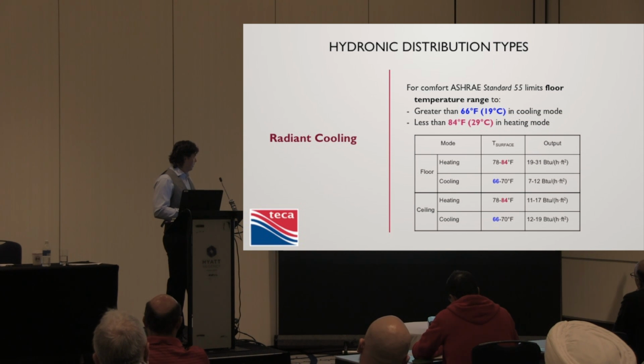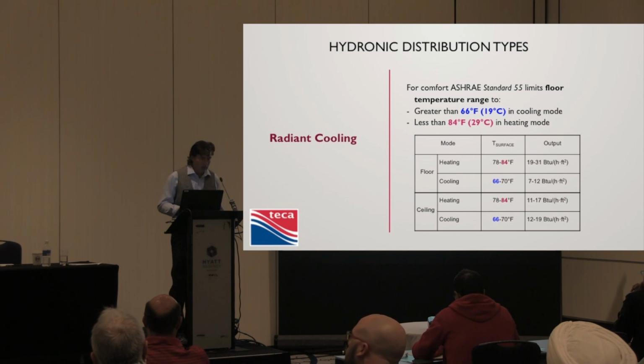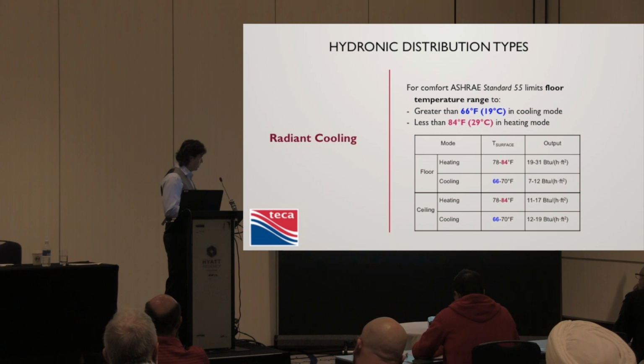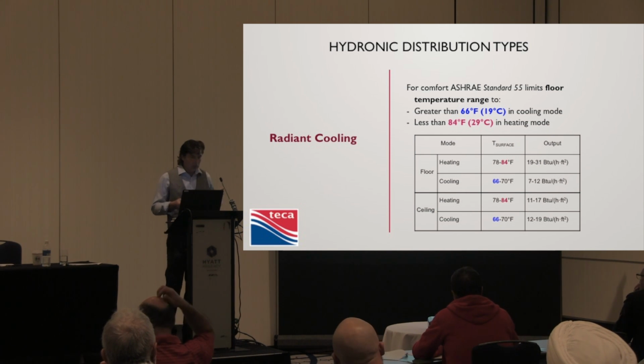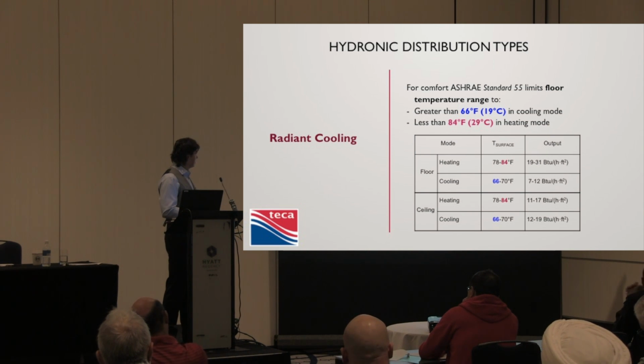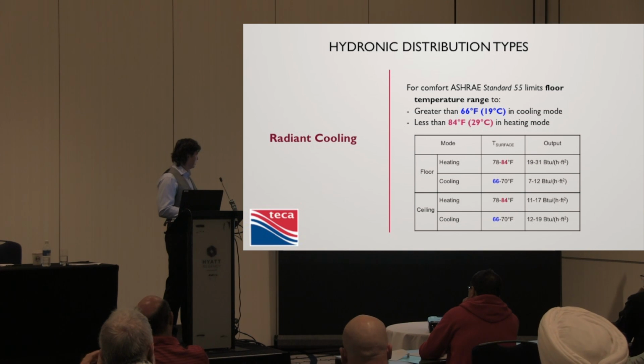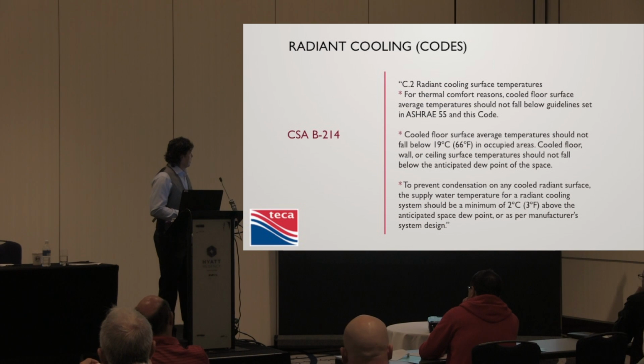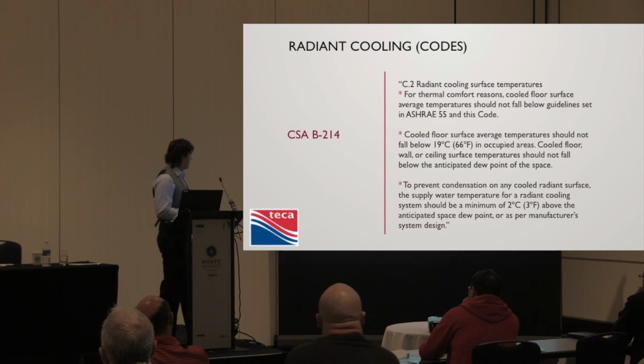In the floor, if I'm in heating mode with 84-degree surface temperature, I can get outputs of 31 BTUs per square foot. In cooling, 12 BTUs maximum. So we have limitations of capacity based on surface temperature and based on condensation levels. So it's one thing to get the floor to this temperature, but it's another thing to make sure that we don't cross the dew point. Same thing with the ceiling. A little bit better on the output. Again, so even the B214 chimes in a little bit on this.